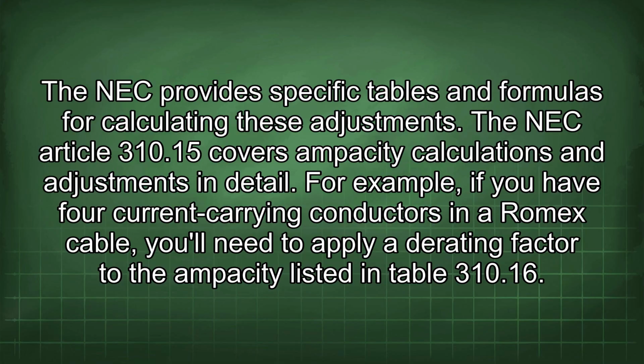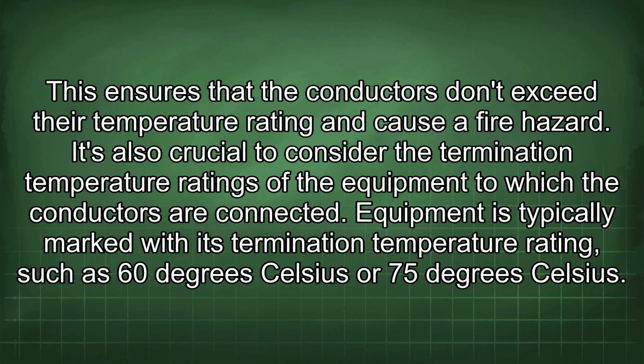For example, if you have four current-carrying conductors in a Romex cable, you'll need to apply a derating factor to the ampacity listed in table 310.16. This ensures that the conductors don't exceed their temperature rating and cause a fire hazard. It's also crucial to consider the termination temperature ratings of the equipment to which the conductors are connected. Equipment is typically marked with its termination temperature rating, such as 60 degrees Celsius or 75 degrees Celsius.